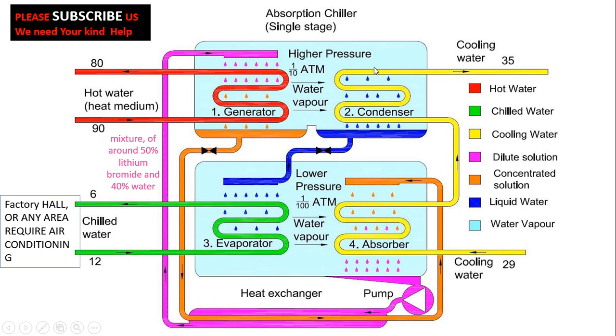In the condenser, there is a cooling coil connected to a cooling tower. When the water vapors strike this coil, they condense back into liquid form. In an absorption chiller, water acts as the refrigerant — so we have now successfully separated the lithium bromide from the water.